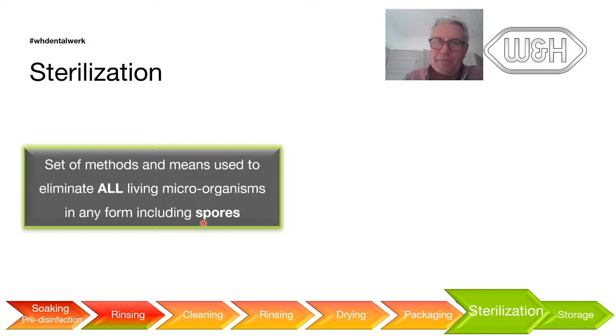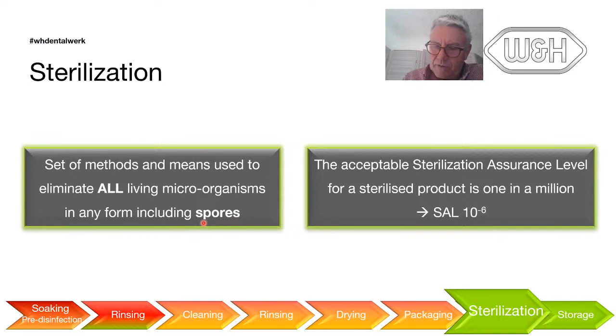Now we come to the last but very important phase: sterilization. It must be a method that guarantees the removal, the killing of all microorganisms, including spores. You remember I talked about bacterial endospores, the most resistant microorganisms. They must be killed. Because despite what we may think, it's never going to be 100% sterile. I mean, there's a tolerance. This is the European standard for sterilization. It says that the survival of microorganisms can be expressed as a probability reduced to a very low number. It can never be reduced to zero.